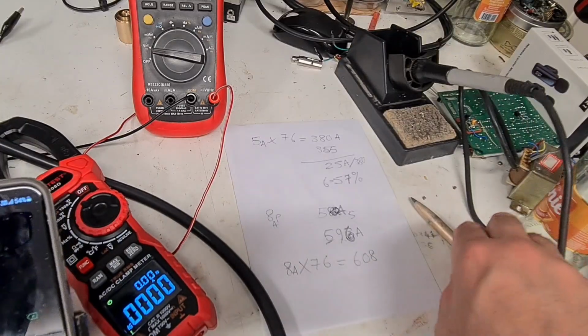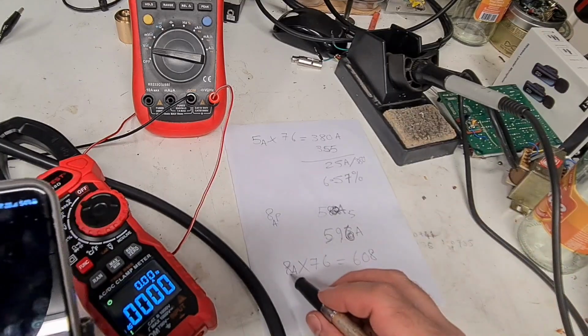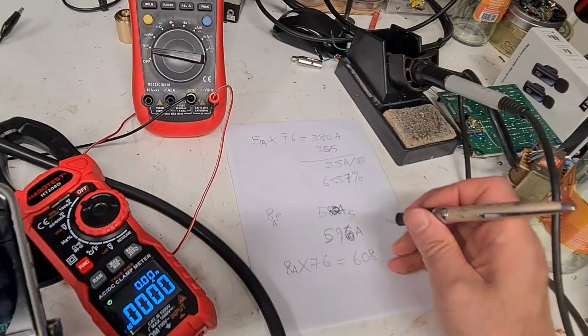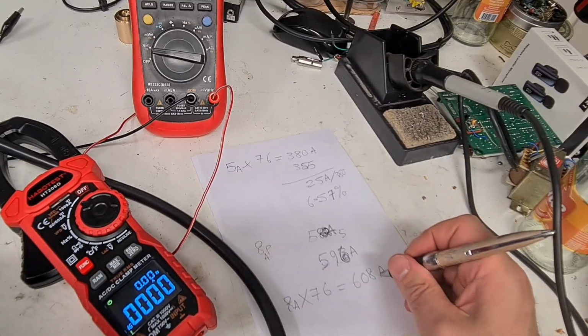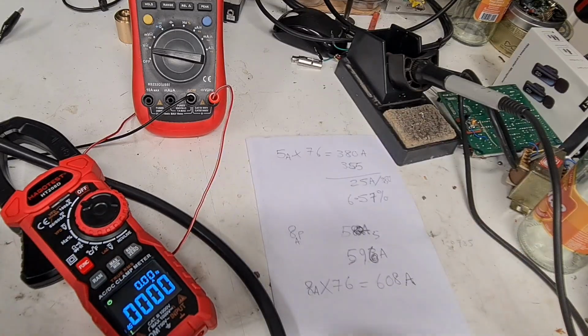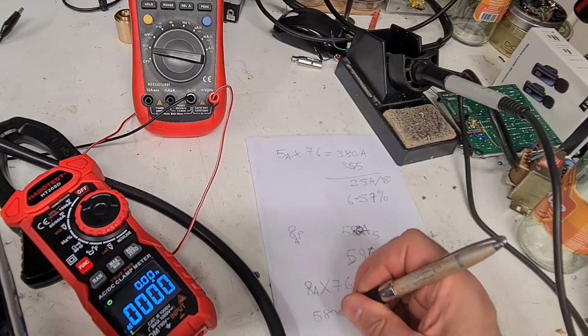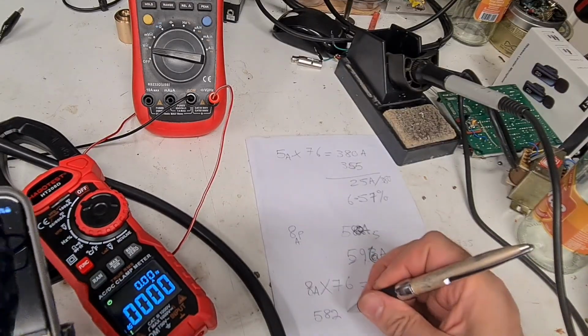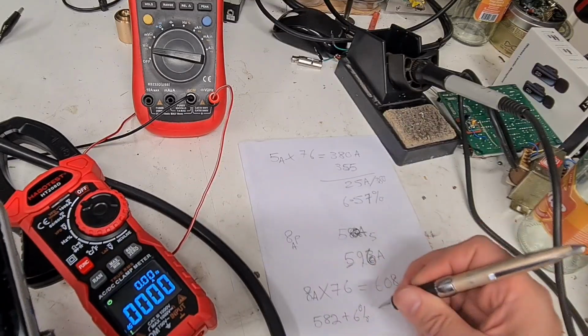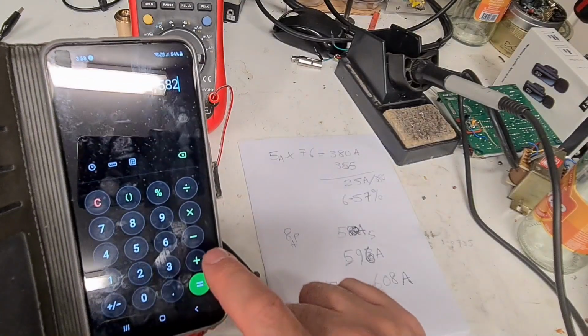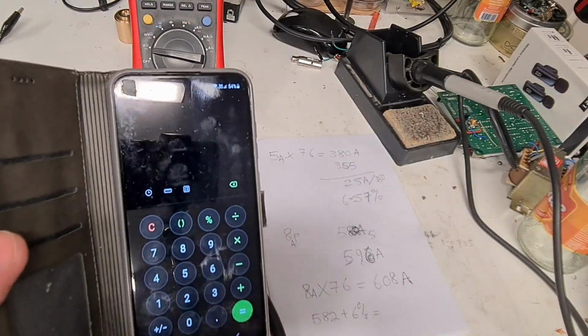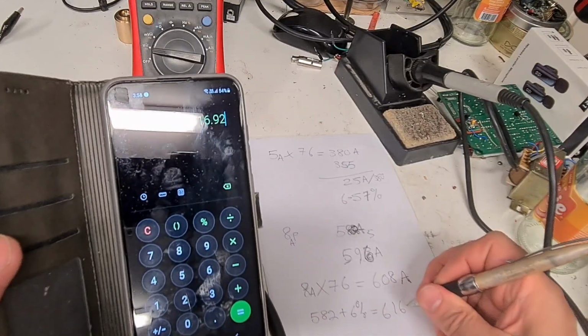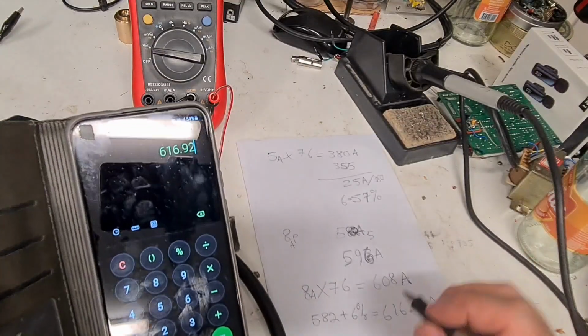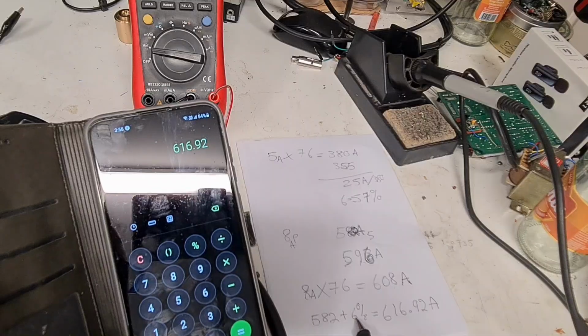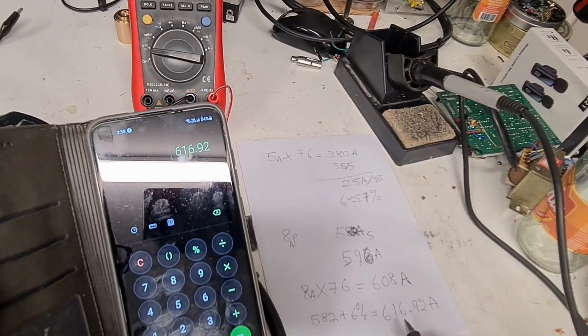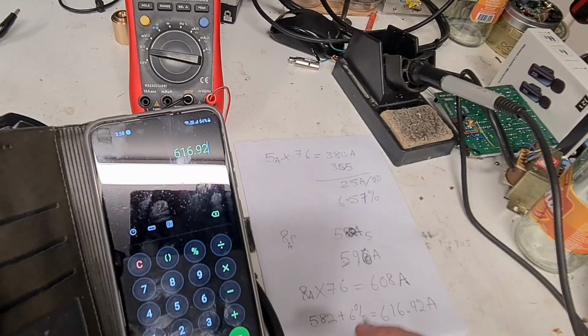So let's do, so 8 amps by 76 of the ratio, we should get 608 amps on the secondary. Okay, and that is full efficiency. So now let's do 582, which is what I've read on the secondary. So if I do 582 plus 6% equals 616. So now 92 amps. You see, as I said in the first place, the percentage is going down. So if I do, let's find out the ratio exactly now, the percentage.